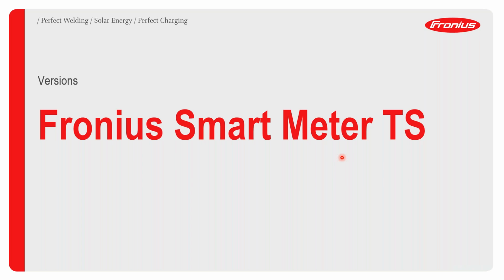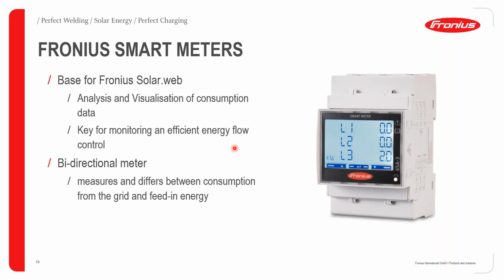We now have a new series of smart meters that we're calling Smart Meter TS, or the Fronius Smart Meter Touchscreen. The biggest difference will, of course, be the display, as you're going to look at later. As I mentioned before, the reason you need the smart meter is that it offers the basis for monitoring and visualization of data in Fronius SolarWeb, and for monitoring and energy flow control. Once you want to think about integrating something like Fronius Ohmpilot, a Fronius smart meter becomes a central component in that setup, because it tells you how much excess energy you have depending on load consumption, and therefore which other additional components or gadgets you can retrofit into your systems. The Fronius smart meter is a bidirectional meter, able to measure and differentiate between consumption, power that you borrow from the grid, and fed-in energy.